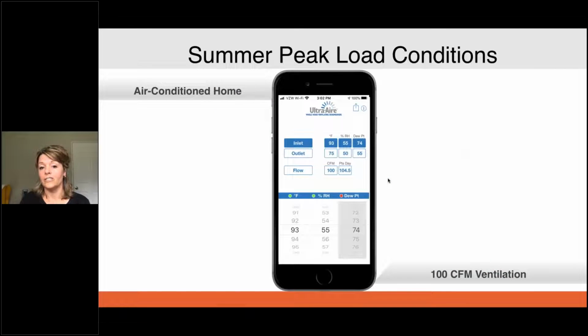So if we look at summer conditions, 93 degrees outside, 74-degree dew point. I want 75 inside with that 55-degree dew point. My ventilation is 100 CFM, and it's telling me how much water removal I'm going to need a day. Now, at these conditions, at peak load in the afternoon, that air conditioner is probably, hopefully, keeping up and doing a good job, depending on how tight the house is, how low load the home is. But it's doing a pretty good job, hopefully, of removing some moisture if it was sized correctly. The challenge is going to be overnight potentially.